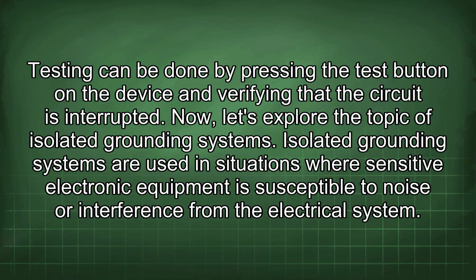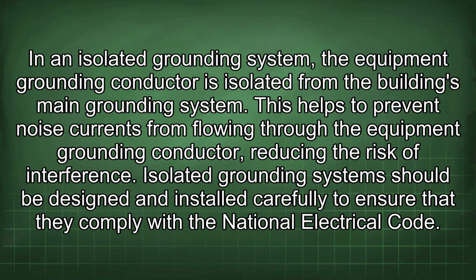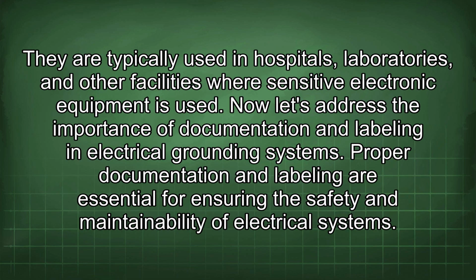Now let's explore the topic of isolated grounding systems. Isolated grounding systems are used in situations where sensitive electronic equipment is susceptible to noise or interference from the electrical system. In an isolated grounding system, the equipment grounding conductor is isolated from the building's main grounding system. This helps to prevent noise currents from flowing through the equipment grounding conductor, reducing the risk of interference. Isolated grounding systems should be designed and installed carefully to ensure that they comply with the National Electrical Code. They are typically used in hospitals, laboratories, and other facilities where sensitive electronic equipment is used.